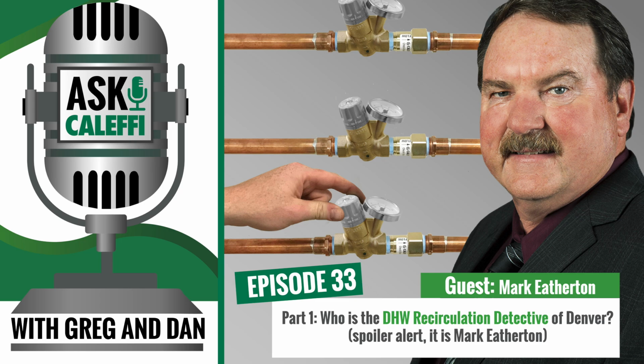The other thing that we're seeing is flux corrosion. The old non-water-soluble fluxes that were petroleum-based are starting to raise their ugly head in that they're causing some holes in some of the copper tubing. It's just an issue that you have to address. It's been addressed in that we are using water-soluble fluxes now that theoretically wash out and won't stay there forever to eat the pipe. But it's the nature of the beast.